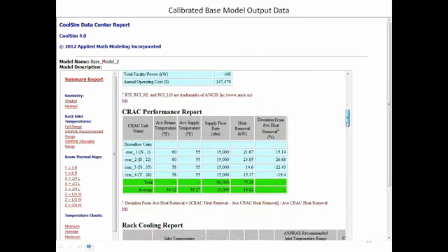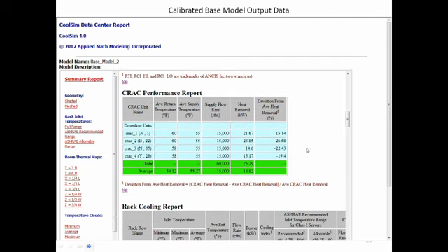So we see here that the CRACs are running at 55, and the delta T's are awful. Look, we've got 5 degrees. Look, we've got 3 degrees across these two. 3 degrees of delta T. Now, what this means is the heat removal's not very much. The efficiency of this unit is lousy. The compressor's running on and off. It's cycling. It's blowing a lot of air. Terrible. Terrible waste of energy.